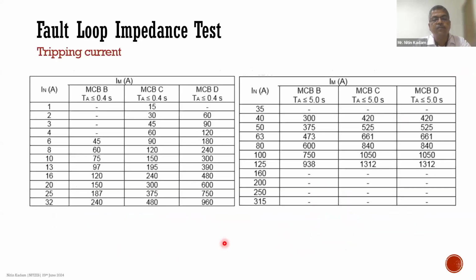In case of the current values for different types of MCBs, MCB type B, type C, or type D, based on the rating, for example, if it is a 6 amp MCB type B, then the tripping current value should be more than 45 amps. If it is a type C MCB, the tripping current value when you do the fault loop impedance test on the site should be more than 90 amps. And in case of type D, it should be more than 180 amps.